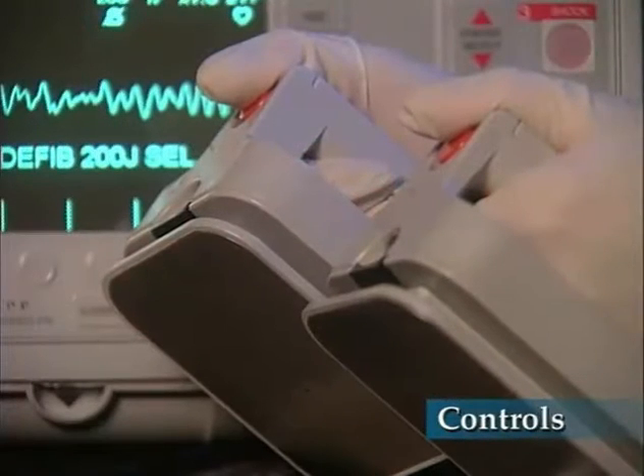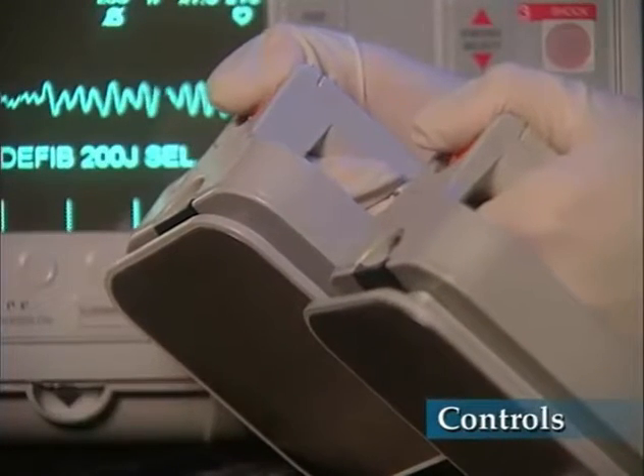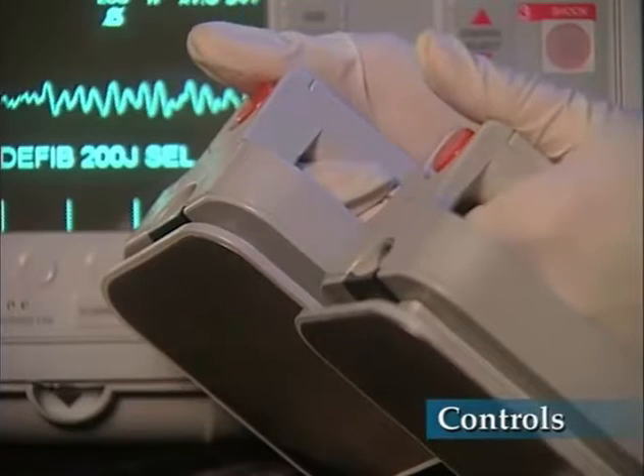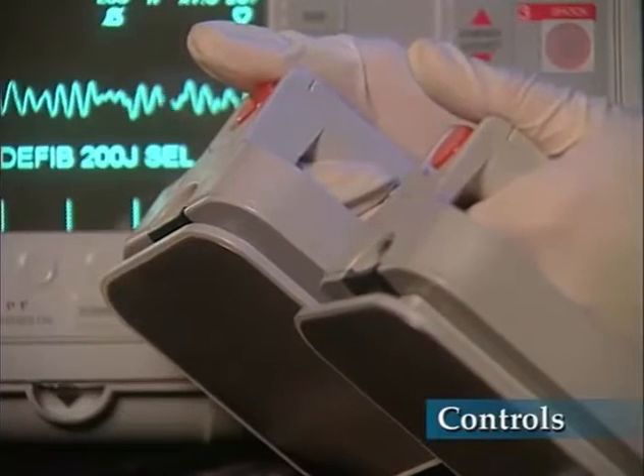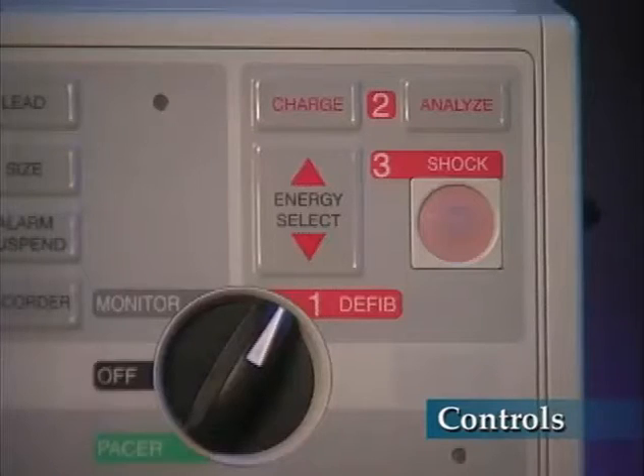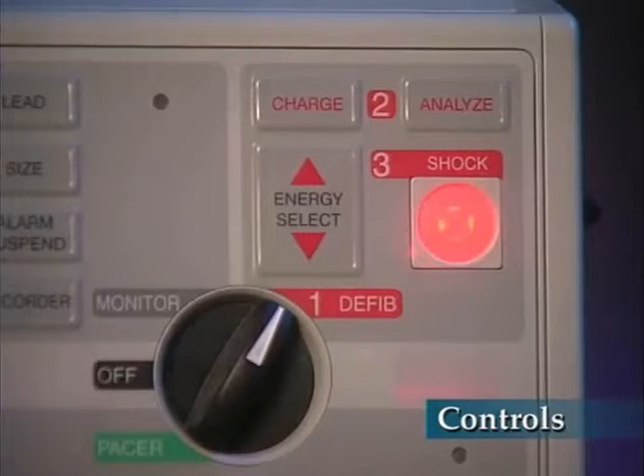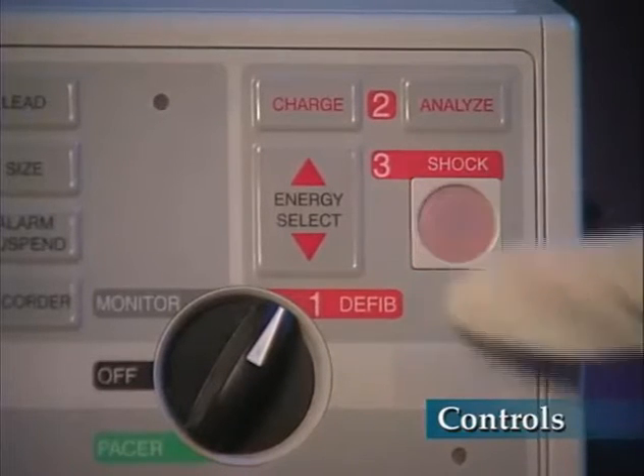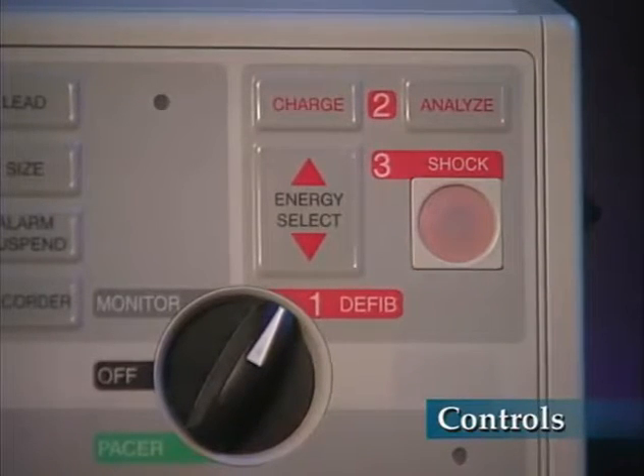Each paddle has a shock button. You must press and hold both buttons simultaneously to discharge the defibrillator when using paddles. The front panel also has a shock button that lights up when the defibrillator is charged and ready. Press this button to discharge the defibrillator when using multifunction electrode or MFE pads.